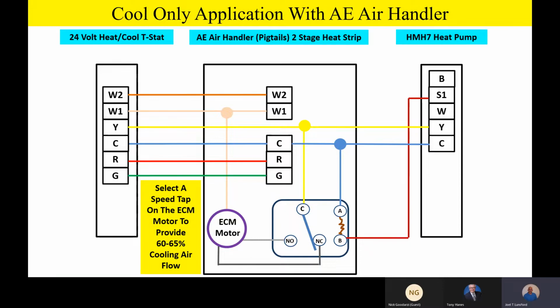So it's going to be wired just like we did before, except we're not going to be taking the B signal outside. And we're utilizing the thermostat to energize the heat strip. And we've got 3 wires outside. So if we've got a straight cool application with an AE air handler, with the airflow reduction capability, we're going to have 3 wires going outside.